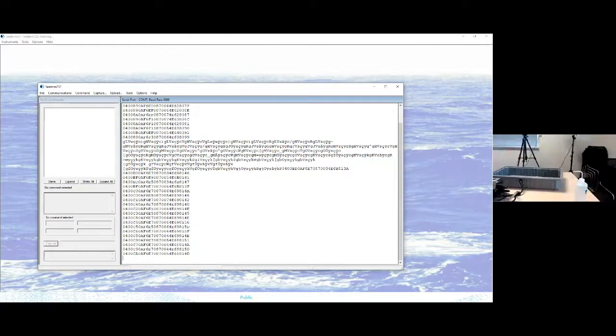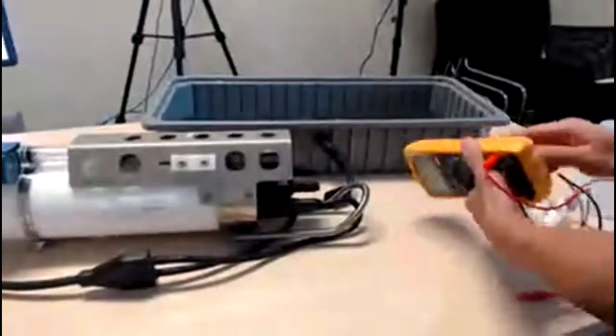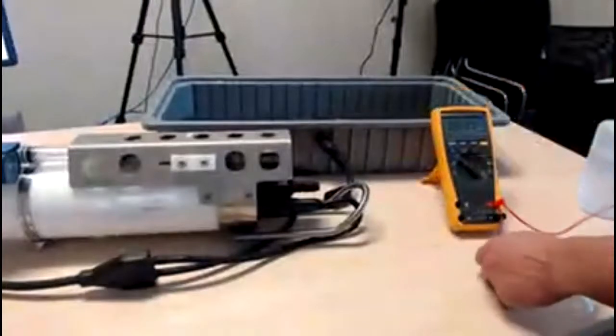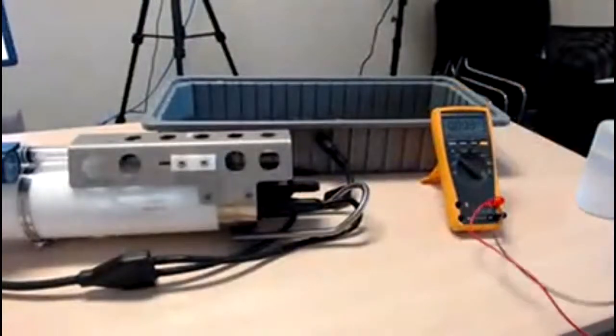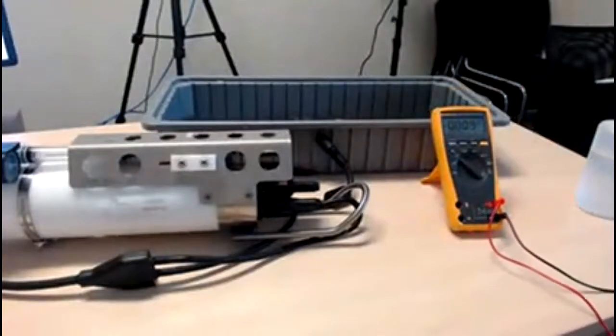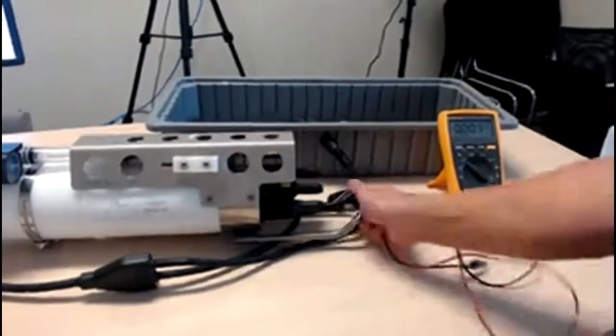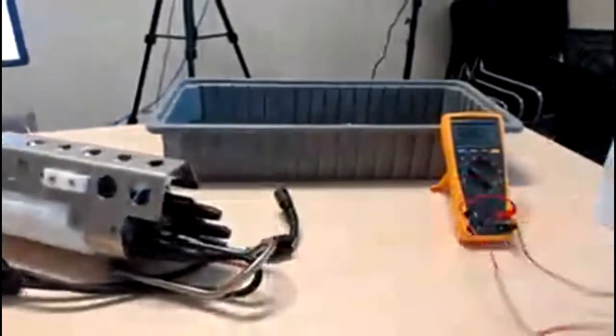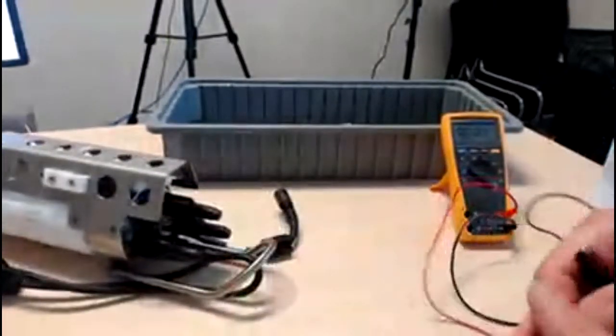The first test is to take a voltmeter and determine that my CTD is actually sending data to the sensor. So I'm setting my voltmeter to measure DC volts. The connector on your CTD is meant to output about 14 volts to power any auxiliary sensor. If it's not doing that, your sensor's probably not even turning on.